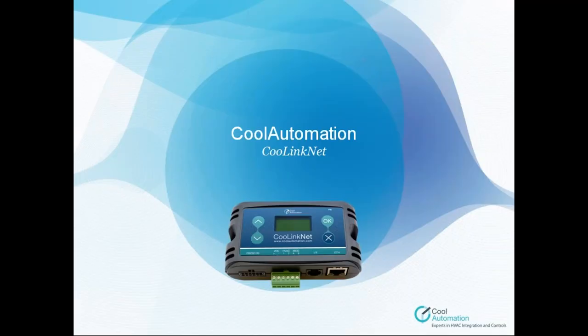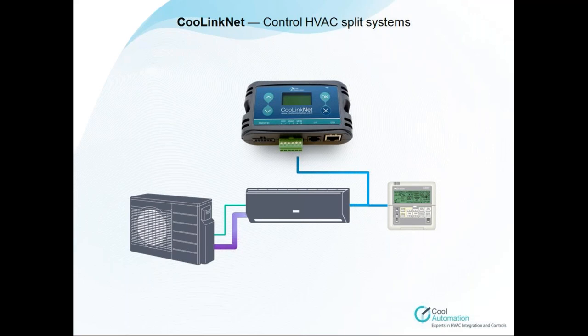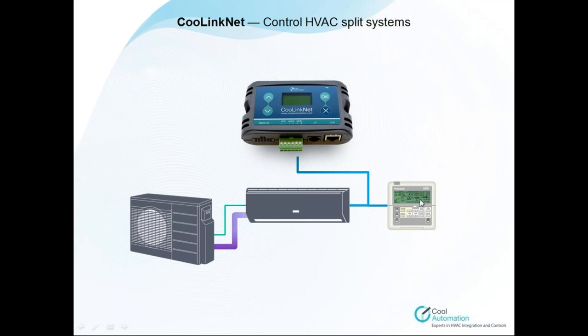Now a short explanation about CooLinkNet. Basically, CooLinkNet works exactly as CoolMasterNet. The only difference is actually it's very big difference. CooLinkNet can control only one unit. CoolMasterNet can control up to 256 different units simultaneously. And of course, CooLinkNet connects to the local interface. CooLinkNet must be connected to the line of the thermostat. The unit itself can be operated from both of them, thermostat and CooLinkNet.